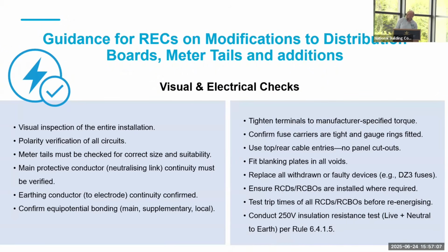Use top rear cable entries and no panel cutouts. So again, what we refer to is an IP rating. So there should be no more than 2 millimeters of a gap on a distribution board. So again, if they do cut out these, we have to insist that they replace it. Fit blanking plates in all voids. Again, that's referring to the one on the top.